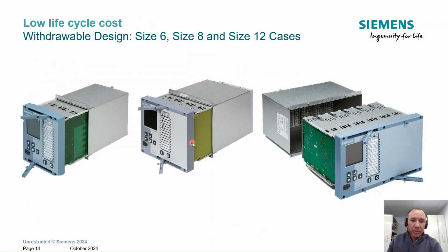As I mentioned, this is the medium size, and that was missing. And this device is withdrawable. If you're going to replace this device for any reason, you don't need to remove any wire at the back. The only wire that you need to remove is the comms, either the fiber or RJ45. You just unplug the comms, and you can pull. There is this lever on top and bottom. You just undo or unscrew the bolts here, and you can pull the device out of the case, and the case stays on the panel. You just remove the core of the relay.